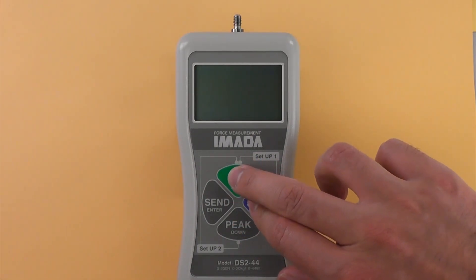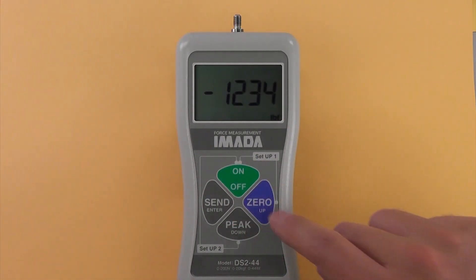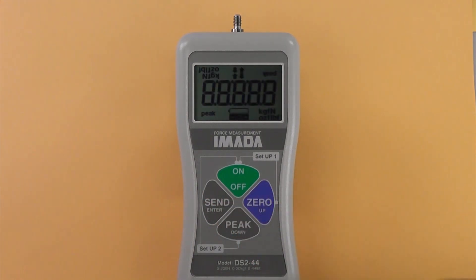Selecting units: turn off the gauge, hold ZERO and press ON once. Press PEAK to cycle between available units, then press SEND to select.